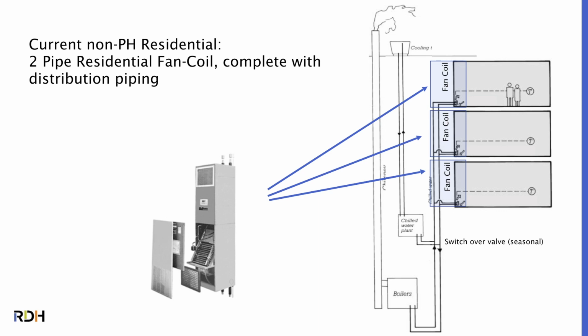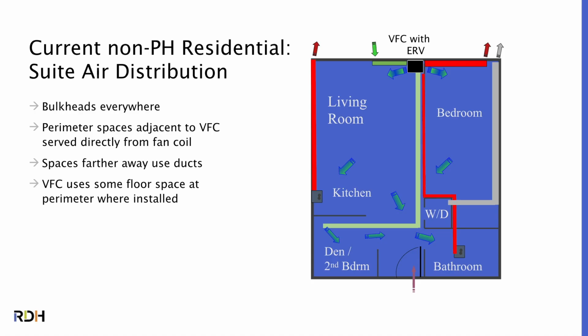Roughly 300 CFM, and we need like 90 to meet our loads. They also end up generating bulkheads everywhere, so this is where the fan coil unit would be, often coupled with an ERV. It could be an integrated ERV or a separate ERV. I would prefer you use a separate ERV, an integrated ERV, almost impossible to balance in one of these things. You end up with bulkheads all over the place to distribute cooling air into the interior.